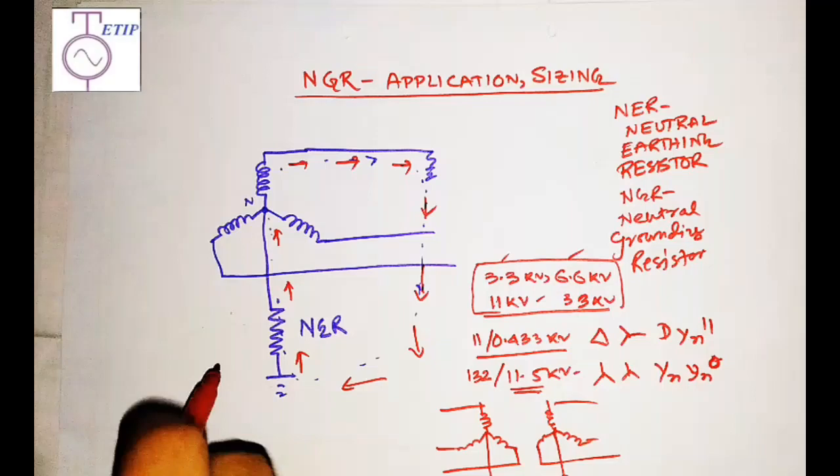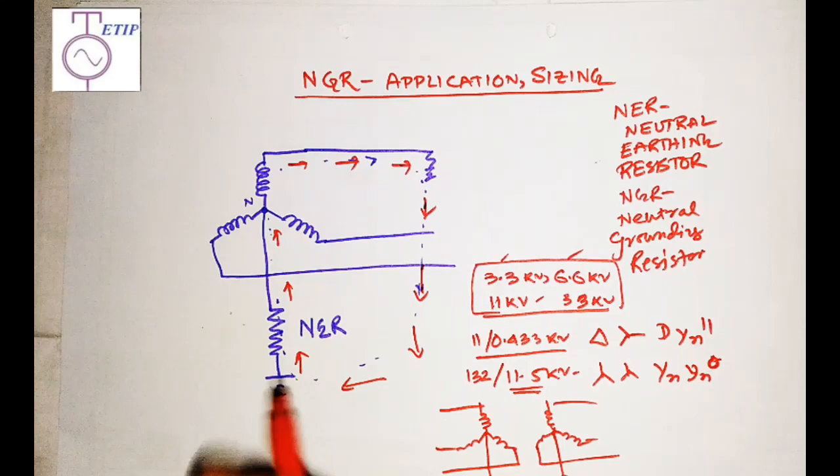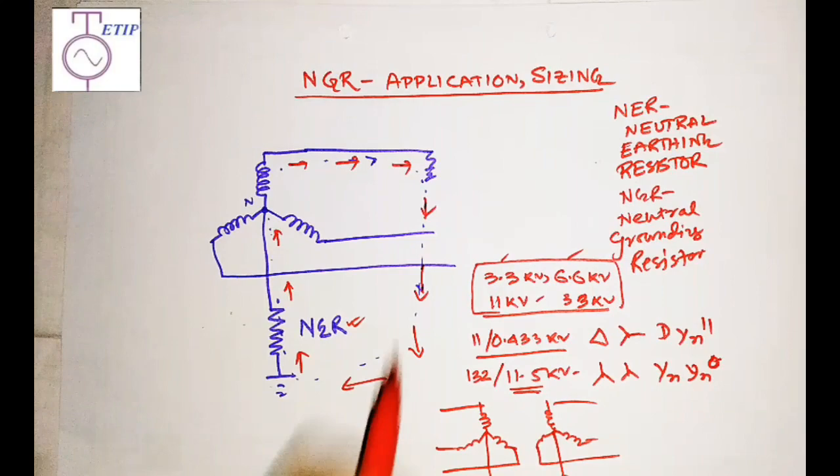Now we will see how the ohmic value of the resistance is calculated. This resistance is placed to limit the earth fault current. There are other methods to limit earth fault current, such as connecting a reactance or earth suppression coil, but NGR is the most common technique used in industry.